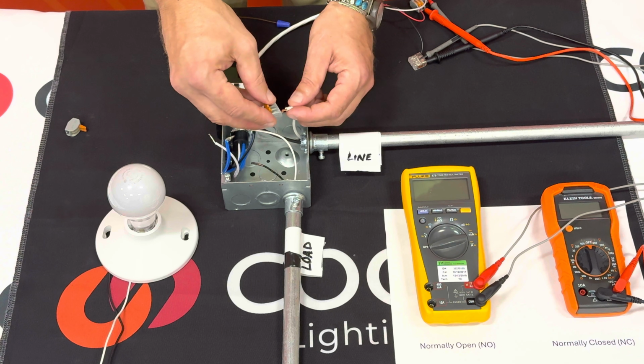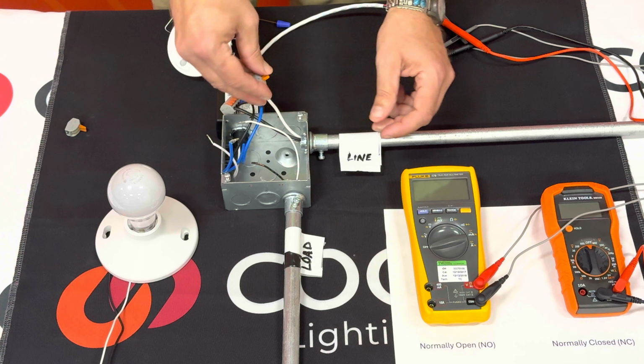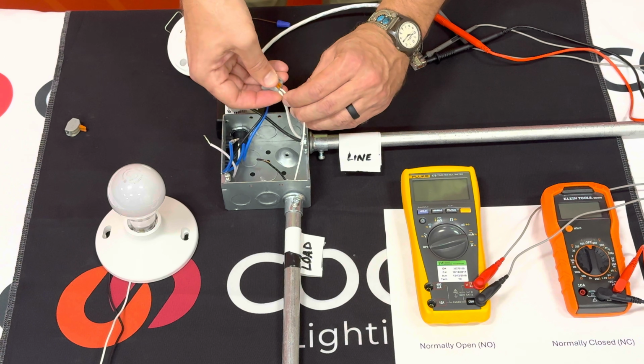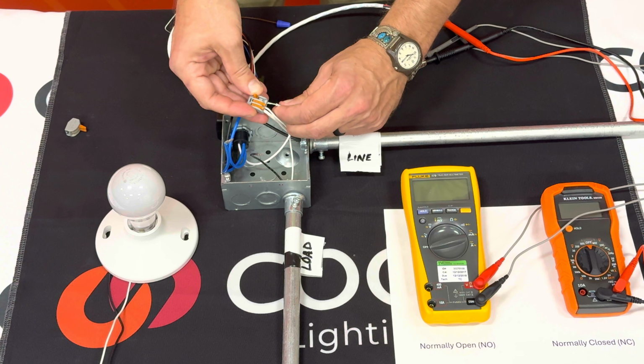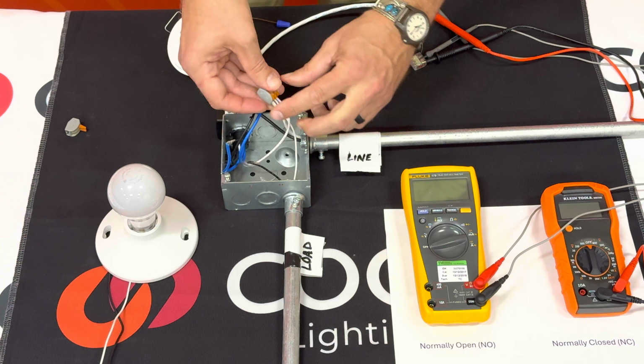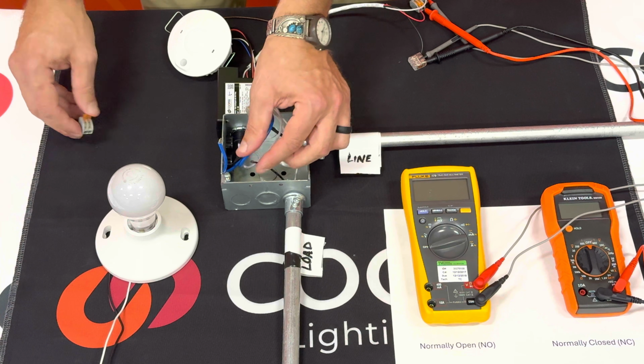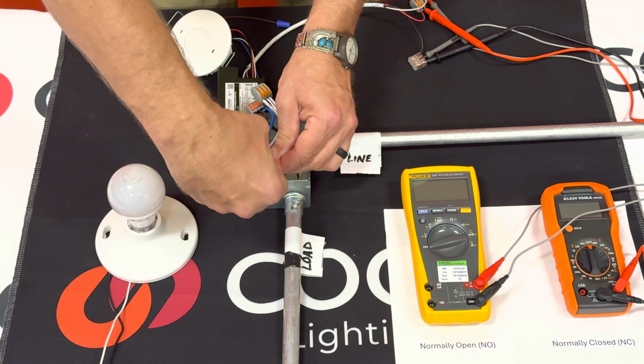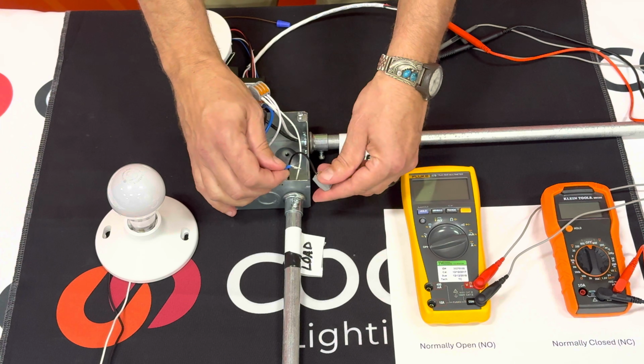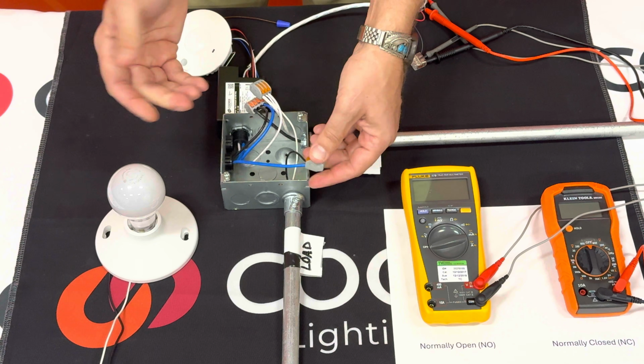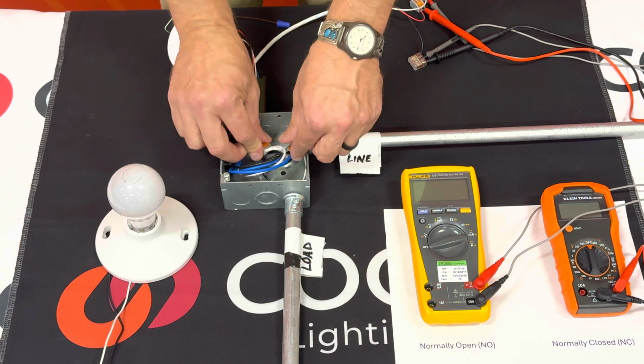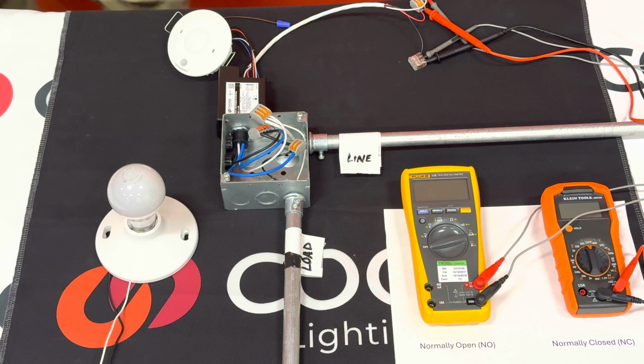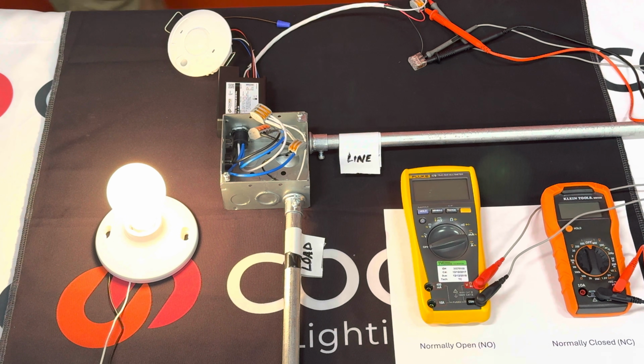Next, connect the white neutral from the source of power with the white neutral of the RSP-V and the white neutral from the load. Finally, connect the other blue from the RSP-V to the black switched leg from the load. When power is applied, the sensor sends a signal to the RSP-V and the load is turned on. This is because the sensor is seeing occupancy.